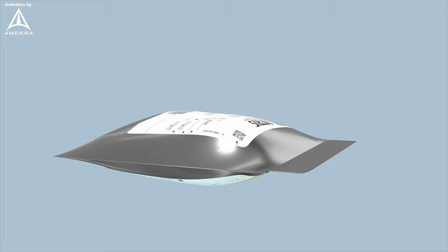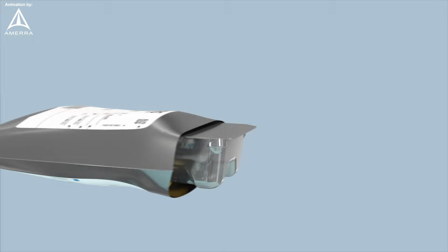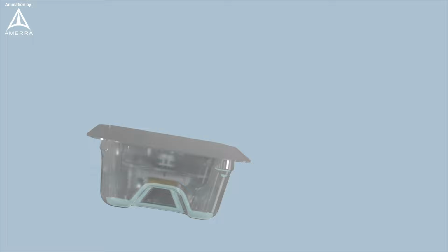Open the foil pouch and remove the outer tray from the foil pouch. Near the sterile field, hold the base of the outer tray. Review the labels, making sure the labels indicate the correct size. After this is confirmed, peel the lid, outer tray Tyvek, from the outer tray. The inner tray and contents are sterile. Transfer the inner tray to the sterile field.